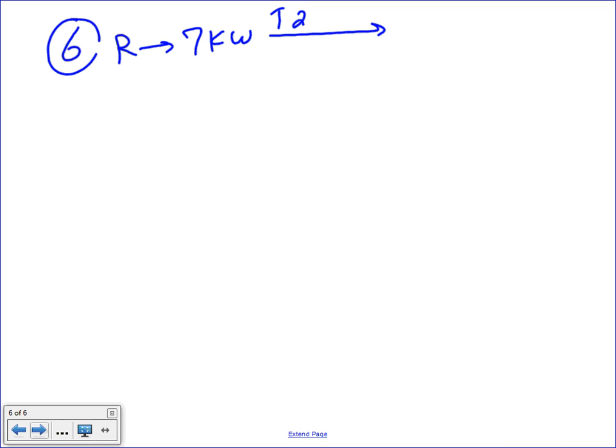220.55, under which column? B. If you go there, take one range, multiply it by 7, multiply it by 0.8. 7 times 0.8 gives me 5.6. That will give me 5.6 kW.